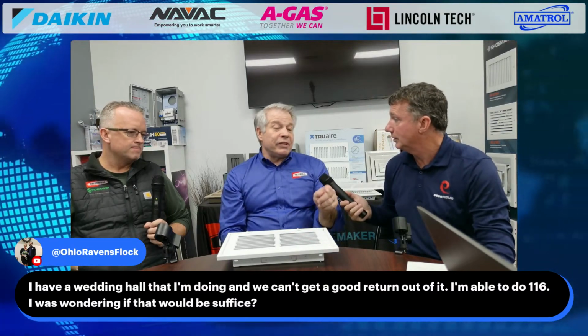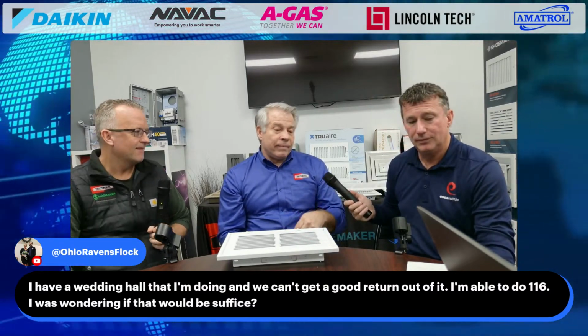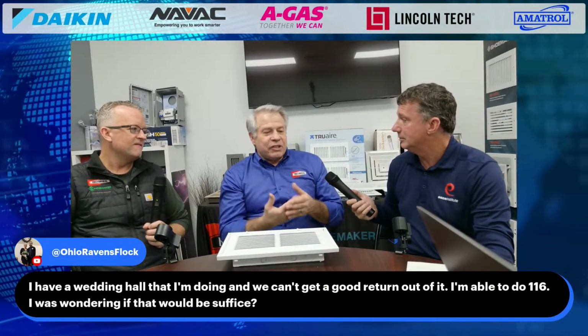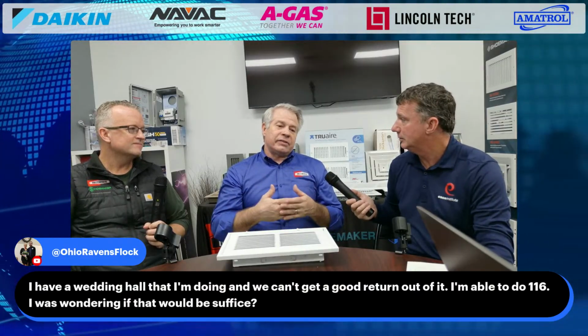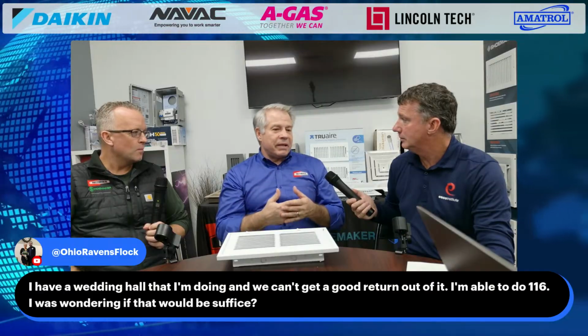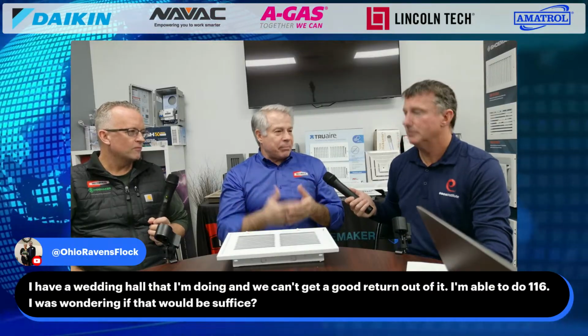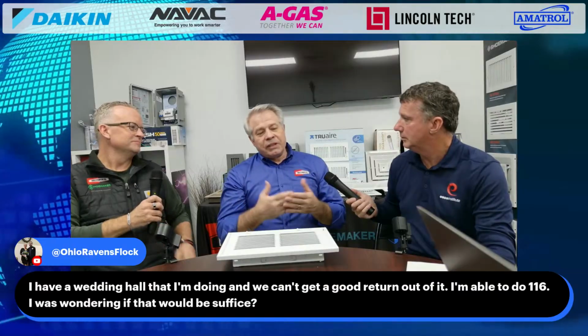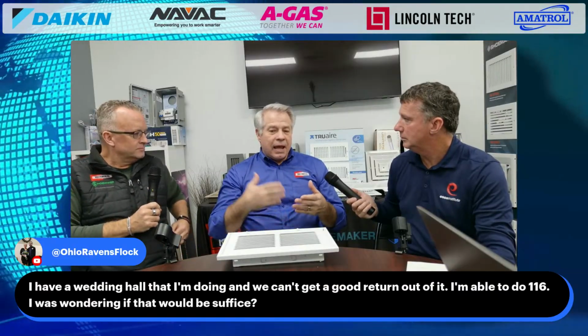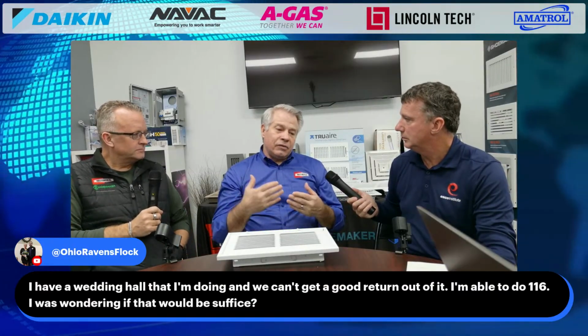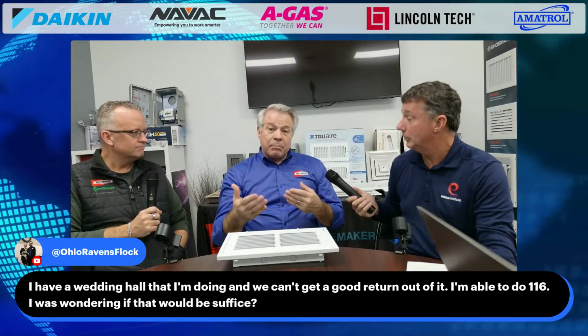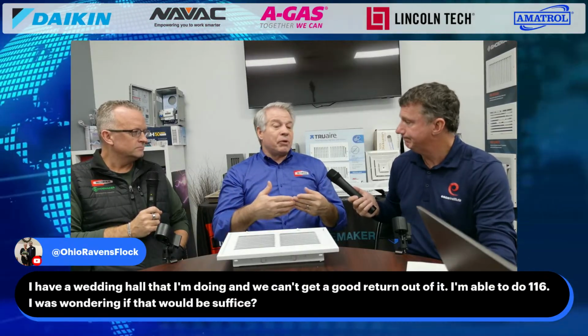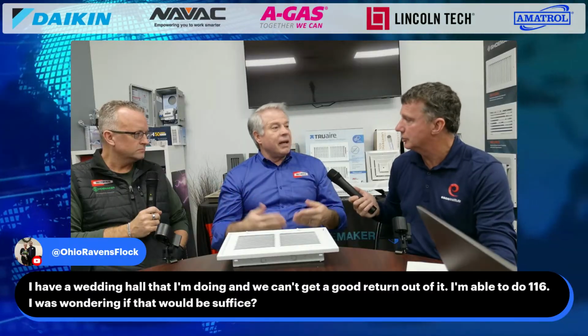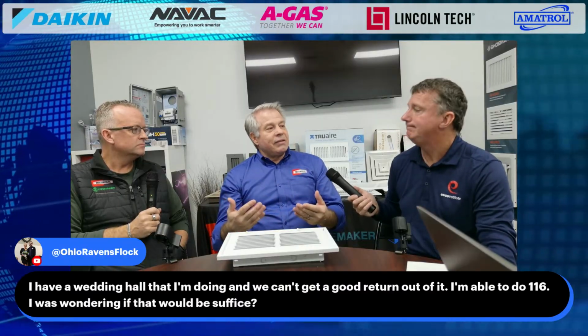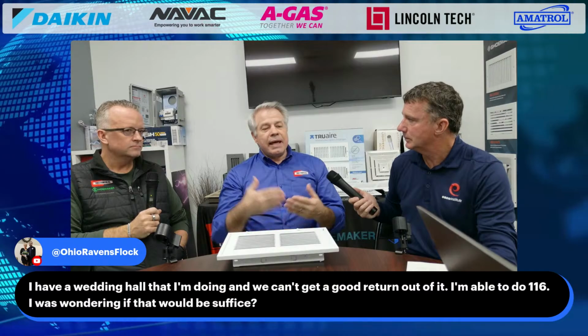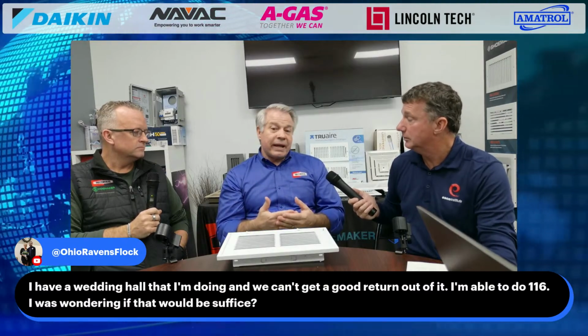And I'm sorry, as I'm reading your note, it's actually a wedding hall. Yes. So let me just put this. ASHRAE has NC levels recommended for different types of applications. Absolutely. So when you look at this, you should start with the ASHRAE handbooks and look up the NC rating for that application. Right. A wedding hall, perhaps a church, it would be the same thing. Sure. And that's where you start with that.